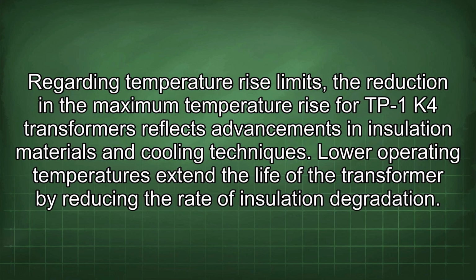Regarding temperature rise limits, the reduction in the maximum temperature rise for TP-1 K4 transformers reflects advancements in insulation materials and cooling techniques. Lower operating temperatures extend the life of the transformer by reducing the rate of insulation degradation.